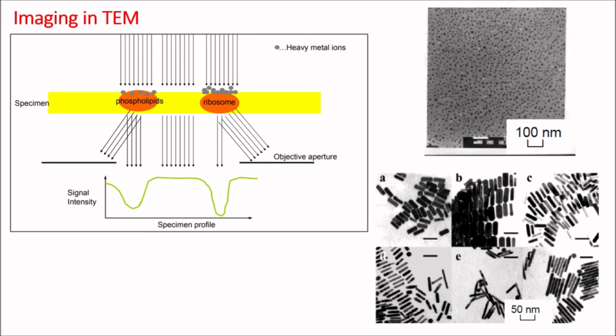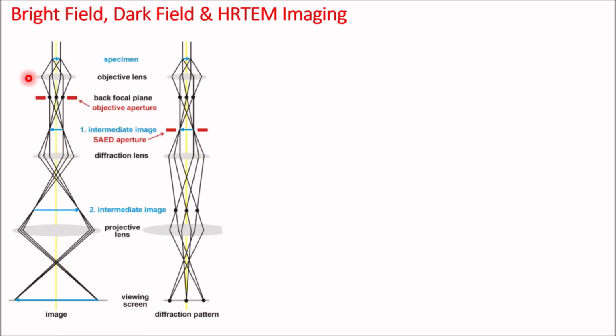The standard CCD cameras for TEM have 2x2K to 4x4K pixels, being sufficient for most applications including biological imaging. The objective lens is positioned below the sample specimen and it represents the most important lens in the microscope since it generates the first intermediate image as well as the first diffraction pattern. The quality of the image formed by the objective lens determines the resolution of the whole microscope.